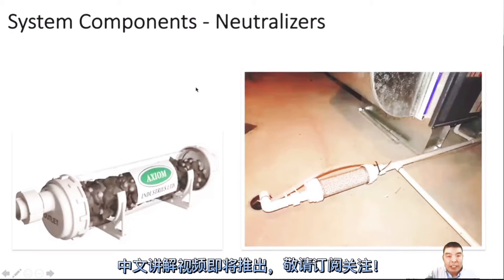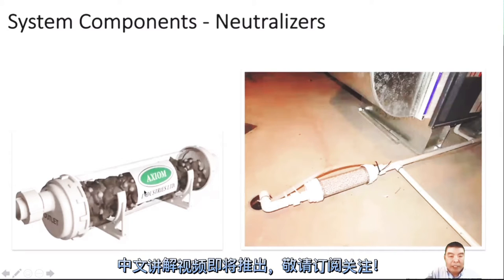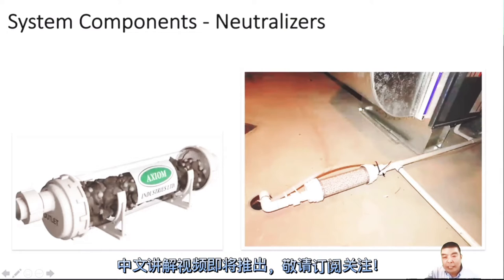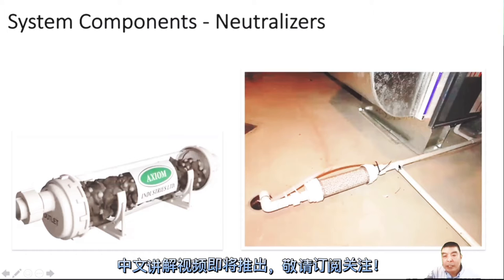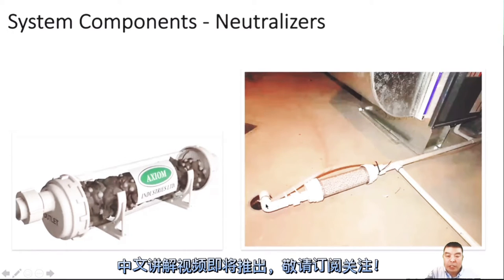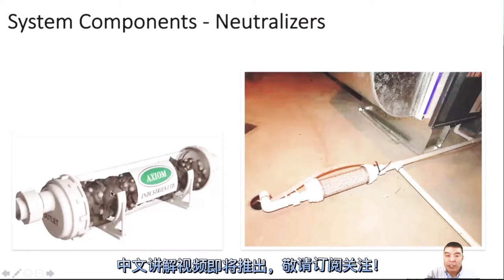This is a neutralizer. In some provinces you may never have seen this, but some provinces require it. If you don't have this neutralizer, as we talked about before, the furnace flue has acid inside — when it melts into the water, the water will be acidic too. So we don't allow the high efficiency furnace condensate water to drain directly to the sump pump — it's not allowed because it damages the pump. Some provinces require a neutralizer before the condensate drain to make the acid neutral.